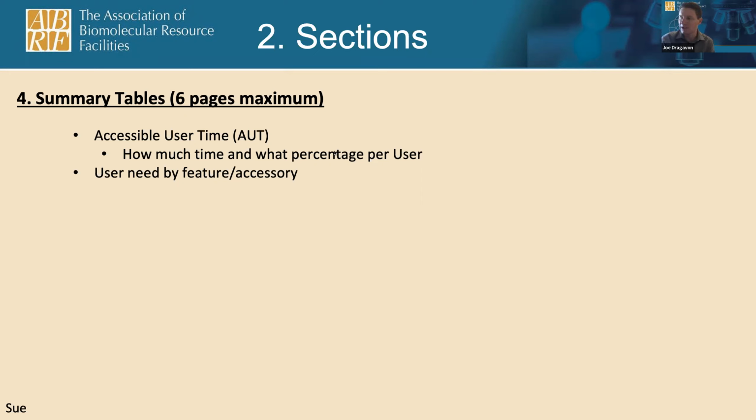The best I've been able to, after talking about it for several years with people, is you want a very logical determination of what your AUT is. You want a good sound logic to it and how it accurately reflects what your users are going to be doing. I remember the AUT, you're starting with some base number. You can calculate if it's an instrument that can operate 24/7, there's X number of hours in a year. You realistically can take off a few weeks for vacation. You can't say it has to be operating during vacation time.